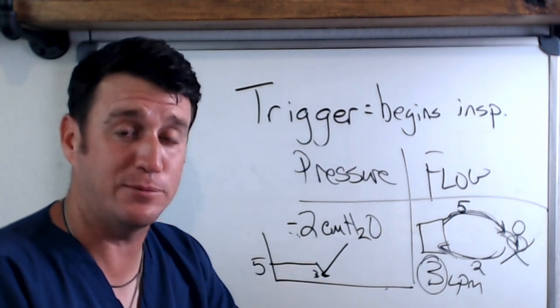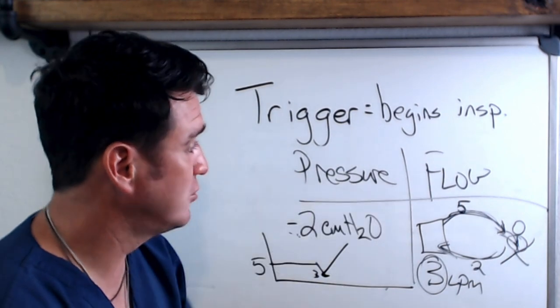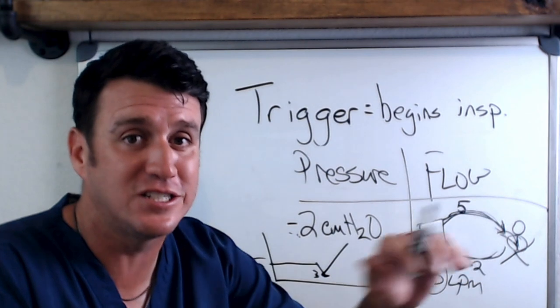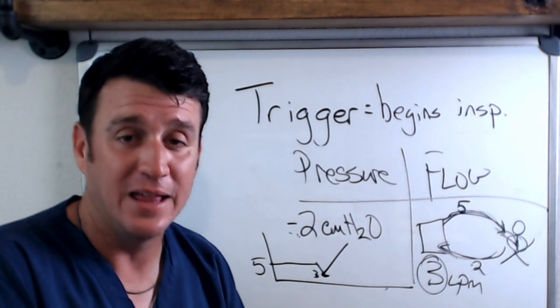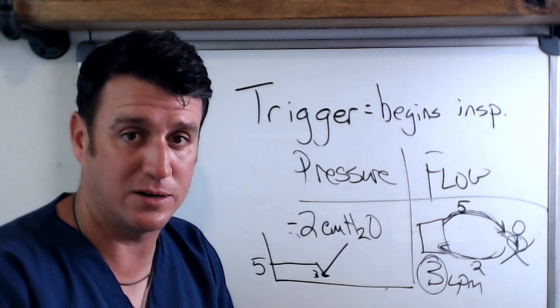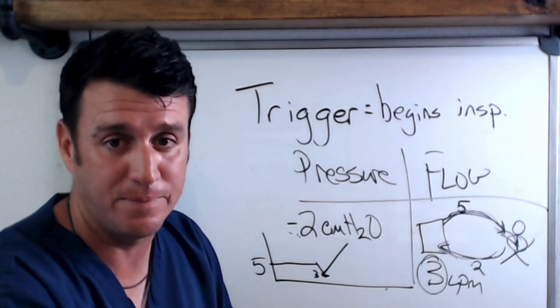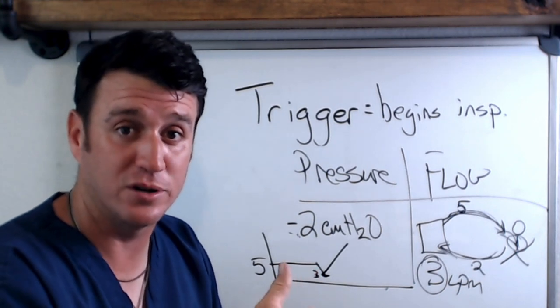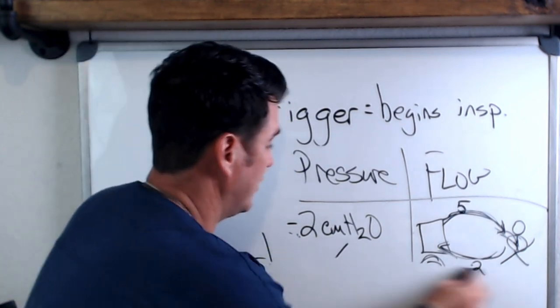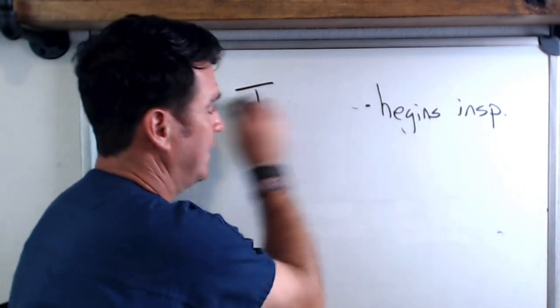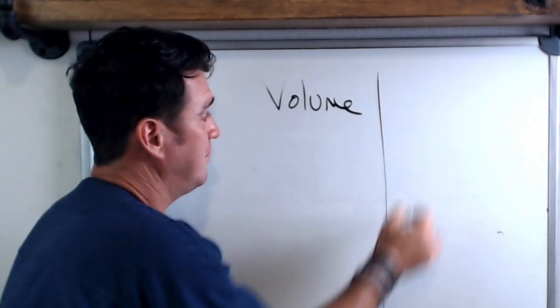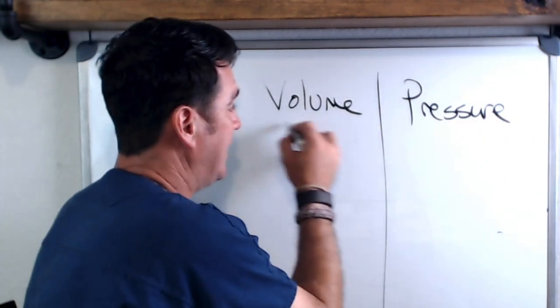You have to understand trigger: time trigger on the vent side, and pressure and flow trigger on the patient side. Pressure, flow, or volume triggering have no effect on the ventilator's time trigger — these are two different types of triggers that are always happening simultaneously. The vent is always operating off a time trigger and is always sensitive to a patient trigger. Once you understand those three terms — trigger, cycle, and limit — you are well on your way to learning specific modes of mechanical ventilation.